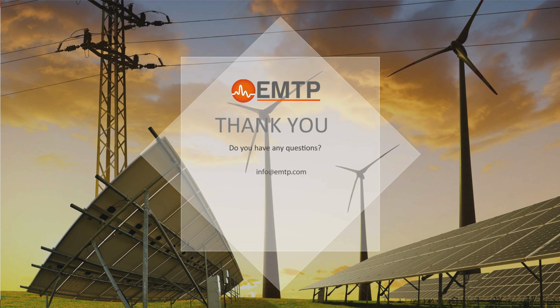Related to the overvoltage levels that can be reached with distributed generation during a ground fault, you mentioned there are situations where we can go beyond 1.7 per unit, right? Yeah, depending on the generation-to-load ratio. Right. Can you explain a little bit the mechanism of how we extend beyond 1.7 per unit?